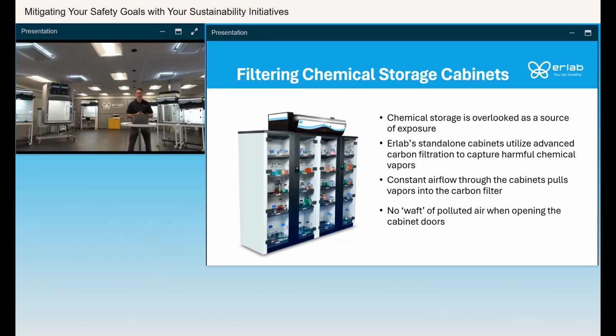So we've taken that same filtration technology from our ductless fume hoods and put it where you store your chemicals. So you constantly have airflow flowing through the cabinet, past those bottles, pulling the vapors that are being released from those bottles up into the carbon filter and returning clean air into the lab. We also, with our flexible filtration column, let you add HEPA filters. So if you are storing any hazardous or toxic powders, you can increase the safety of that by having the filtered cabinet. We have our own standalone, which in this picture is our 1634.